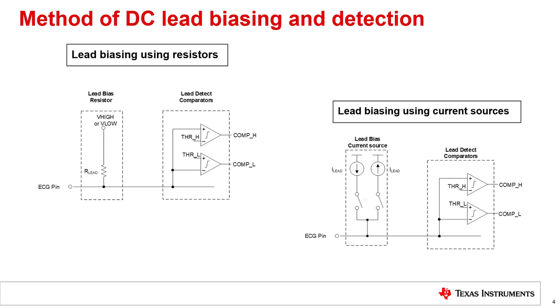In addition to lead biasing, a mechanism is also required to detect the leads-on and leads-off condition. A pair of high-side and low-side comparators can be used to compare the voltage at the pin with a high and low threshold voltage, respectively. Lead biasing using the resistor or current source causes the potential in the leads to be different between a leads-on and leads-off case, and lead detection using the comparators enables detecting the potential and determining whether the leads are connected. This mechanism is referred to as DC lead detection, since the bias is applied to the leads in a DC manner.